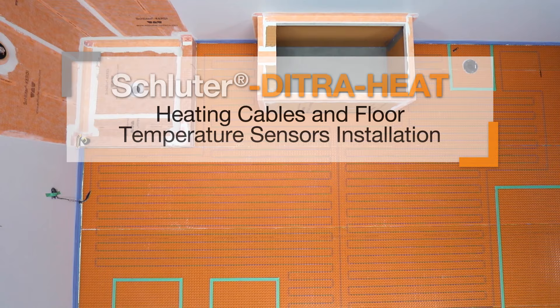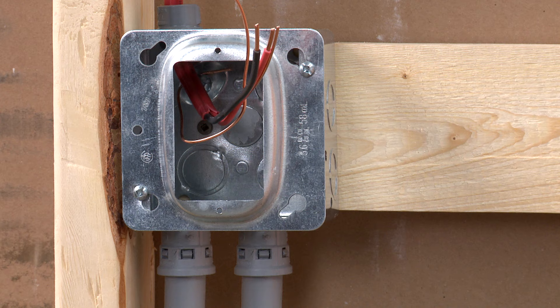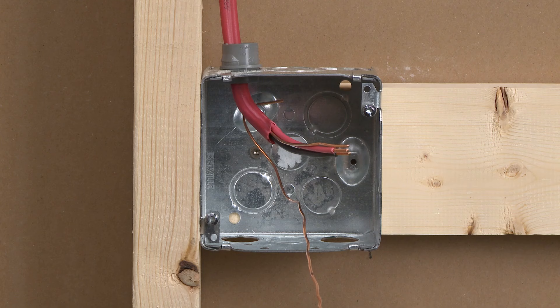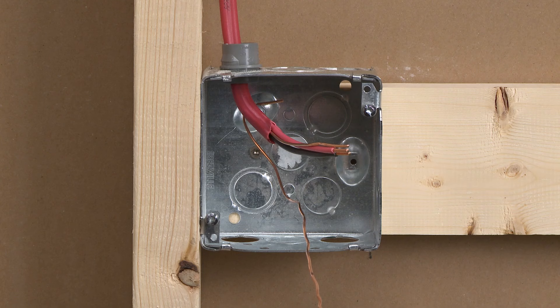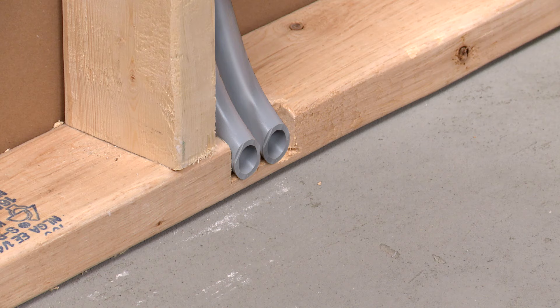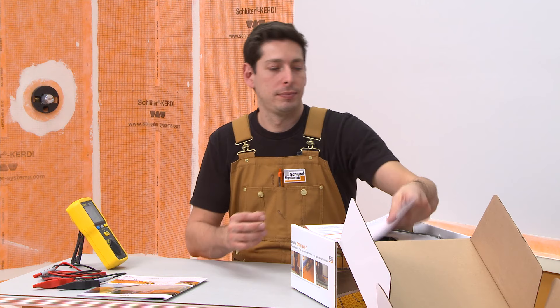This product must be installed by a qualified person in accordance with the installation handbook and with the National Electric Code or Canadian Electric Code Part 1 as applicable. All electric connections must be made by a qualified electrician according to the electrical and building codes effective in your region. The electrical circuit for the heating cable has been turned off. In this application, we will use the DITRA-HEAT E-RT thermostat mounted on a double-gang electrical box with a single-gang mud ring. Two sections of conduit were run from the electrical box to the base of the wall to protect the heating cable cold lead and floor temperature sensors. Each heating cable is subject to factory quality control.